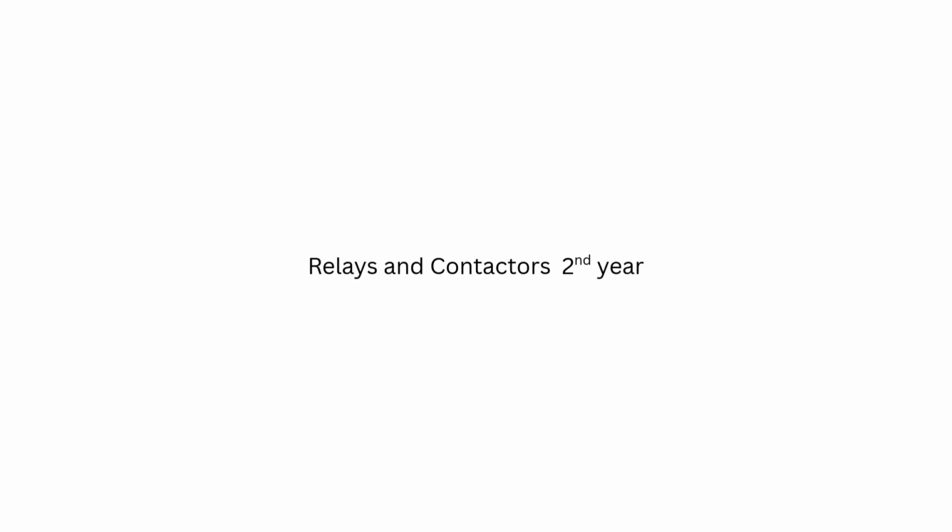Exactly. We should also touch on specialized stuff like low voltage lighting relays. Oh, yeah, latching relays. You hit a coil for a split second to close the contact, and then you hit a second coil to open it. No constant power draw, which is great. And a quick note on terminology for our Canadian listeners. The industry calls them low voltage, but under the Canadian Electrical Code, the CEC code, they're actually extra low voltage if they're below 30 volts AC or 60 volts DC. That's a crucial distinction for installation rules.